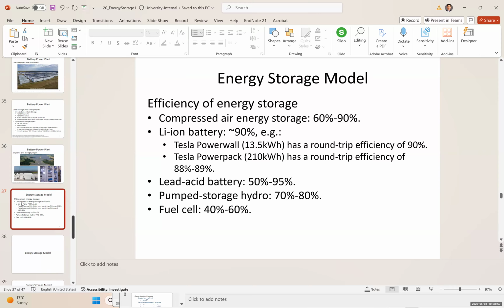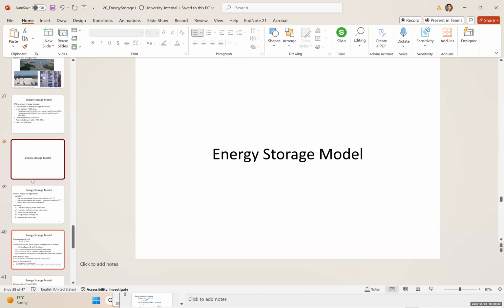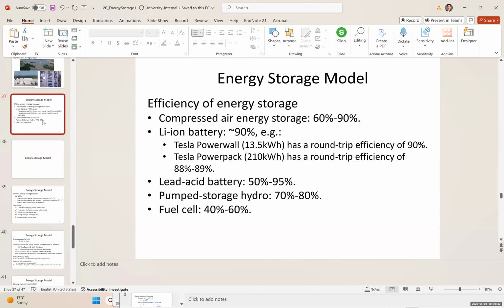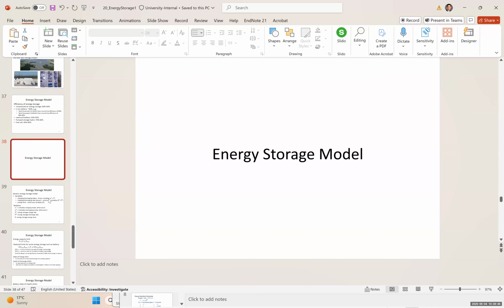The Tesla Power Pack, or the 210 kilowatt hour, has a round trip efficiency of 88 to 89%. The lead acid battery has 50 to 95% efficiency. Pump storage hydro is 70 to 80. And fuel cell is 40 to 60. So you can see the best efficiency is lithium ion batteries. It doesn't have any mechanical parts, so less maintenance. And also now it's become even cheaper than any mechanical based storage system. If it becomes like 30 or 40% cheaper, it's going to replace all the other energy storage systems.